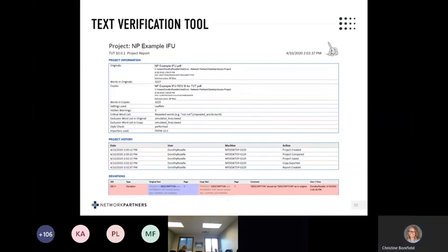When your deviations line up with your intended changes, which could be that you added an IFU document number to the header of each individual language, or you added the ISO country code or ISO language code to each language, you print out, sign your report, and attach it as objective evidence to your change notice and move on to the next file.